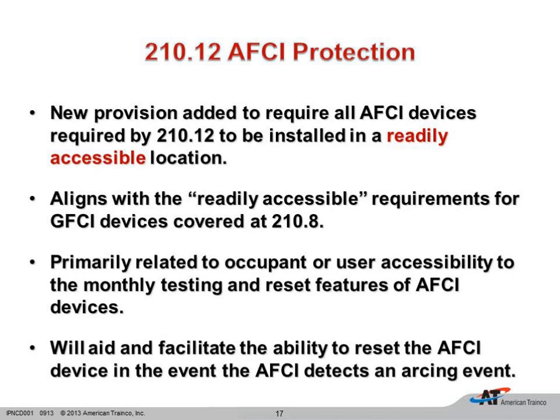And so if I have a metallic wiring method, I can put the receptacle, that is an outlet branch circuit AFCI, at that first receptacle in my circuit, and they feel that the metallic wiring method is going to protect that portion of the circuit from any arcs. And once we get to the first receptacle, then that AFCI outlet branch circuit type device will protect the rest of it.